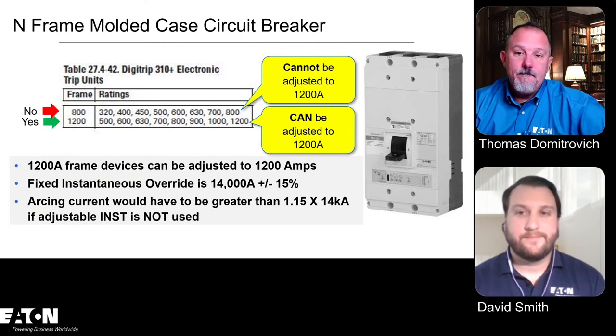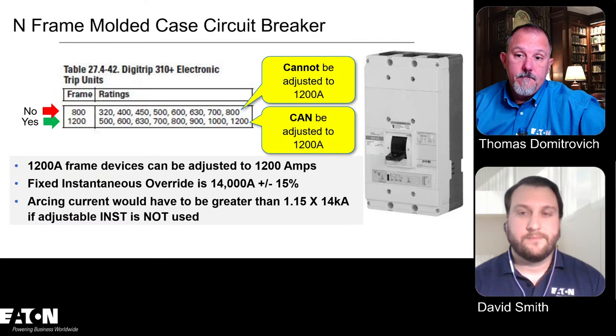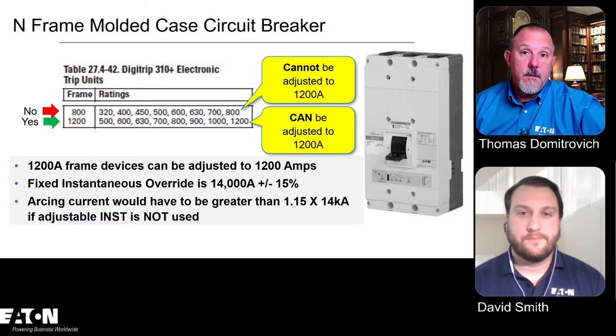But that first one does not need arc reduction technology, because it's an 800 amp frame N frame breaker and cannot be adjusted above 800 amps. The other one I can adjust all the way down to 500 amps, but because I can adjust it to 1200, you would have to have an arc reduction maintenance technology on it. And look where the instantaneous override is on it: 14,000 amps.